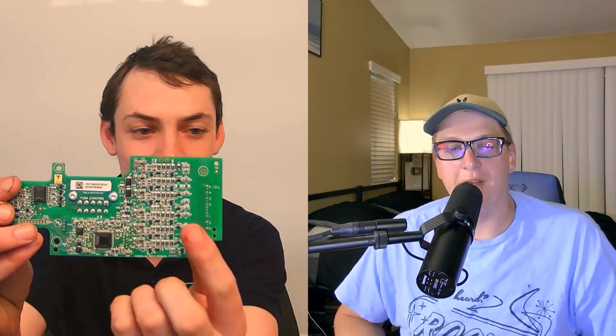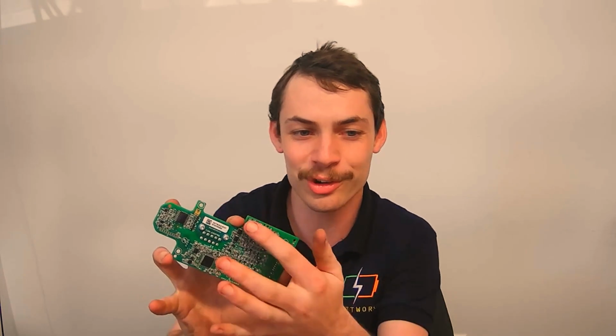If you look at this board, these 2 capacitors right here, C26 and C27—there's a little plastic flap in the pack that rubs the conformal coating off of those. Then if there's enough moisture in the pack to condensate, it likes to condensate right there, causing corrosion on those capacitors. That makes it so the pack can't measure the voltages on 2 of the bricks. That's a super common failure mode on older Model S packs.